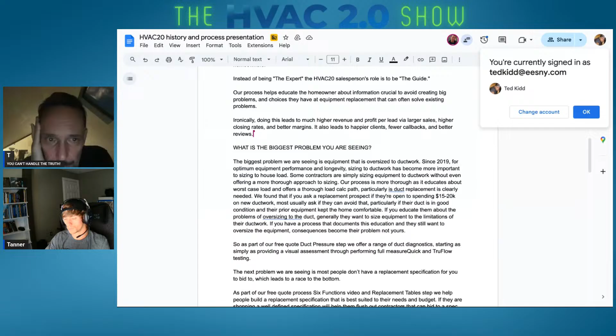The biggest problem we're seeing is equipment that's oversized to ductwork. Since 2019, for optimum equipment performance and longevity, sizing to ductwork has become more important than sizing to house load. Some contractors simply size equipment to ductwork without offering a more thorough approach. Our process is more thorough, as it educates about worst case load and offers a path to a thorough load calc, particularly if duct replacement is clearly needed.